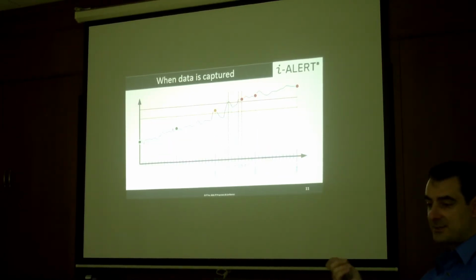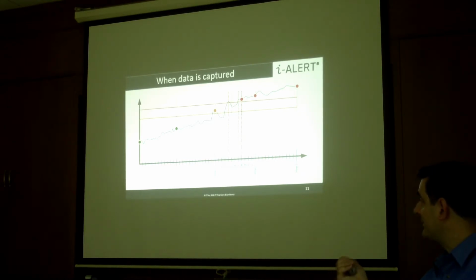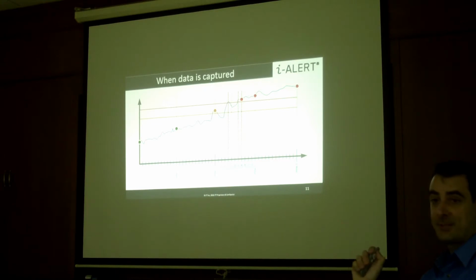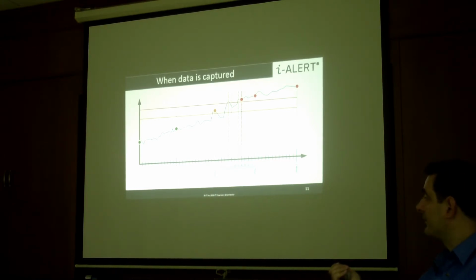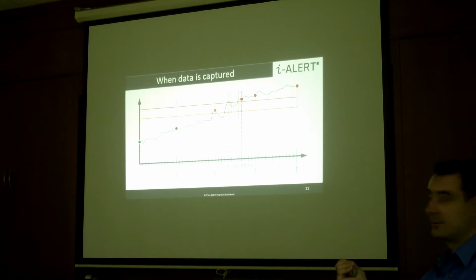Just to clarify, this graph is pretty good for showing you when a data point is collected. Everywhere you see a dot, that's where we save a piece of data. So, if it's healthy, green, you get 1 point here, and then 1 hour later, you get another point. Save. The pump vibration can go up and down, but you get that. If the vibration was to cross the alarm warning level, you will only get the point if it crosses at the 1 hour interval.